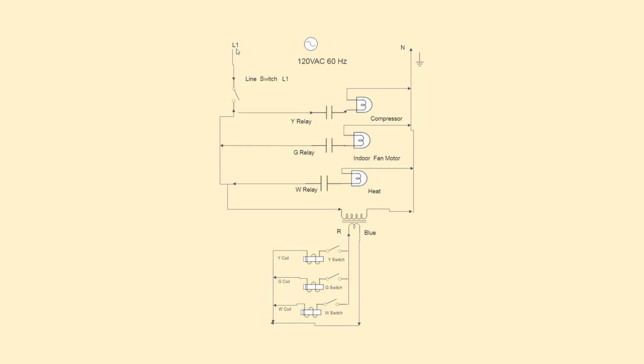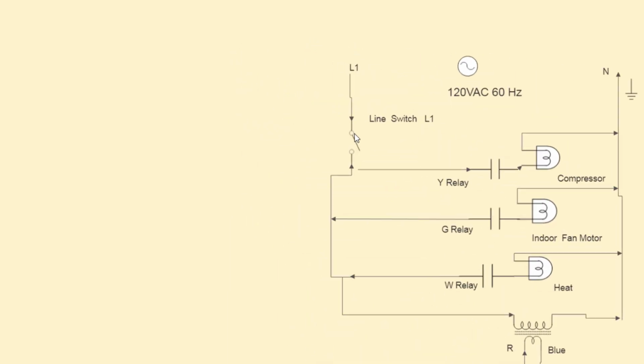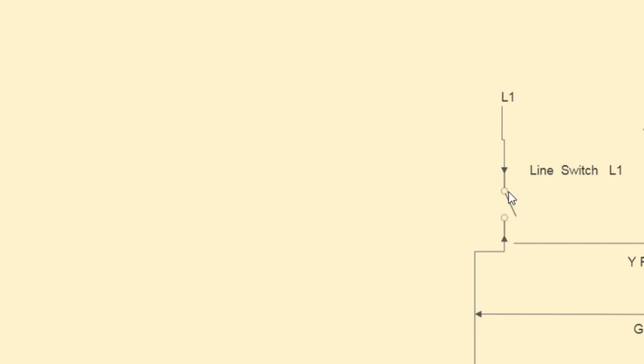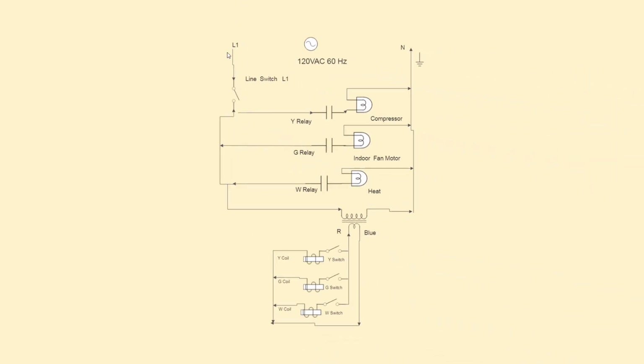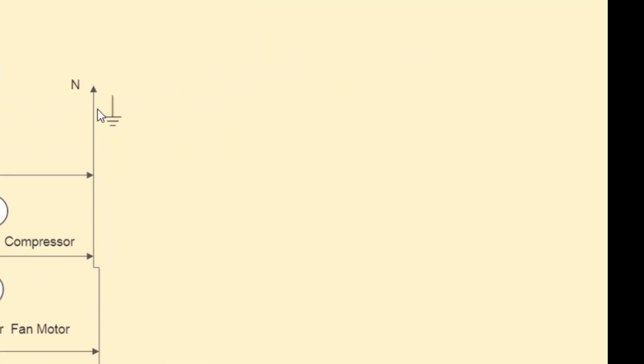You should have a line switch, which I'm pretty sure all of you do. The line switch, remember, has connected to it just the L1, that black wire. It should be 16 AWG. Remember, AWG stands for American Wire Gauge. If it's a thicker wire than 16 gauge, then you're working against yourself because it's harder to use. That's what's going on with this L1. Over here, the neutral return should be a white wire, and that would be 16 AWG as well.